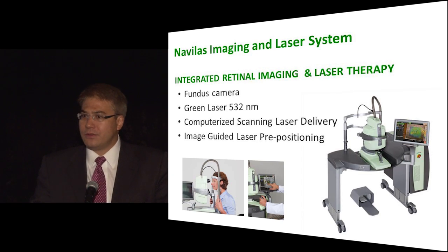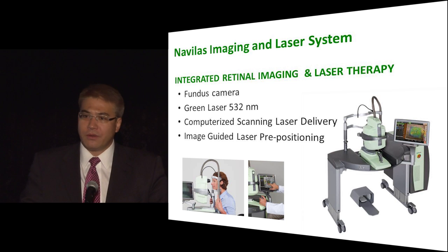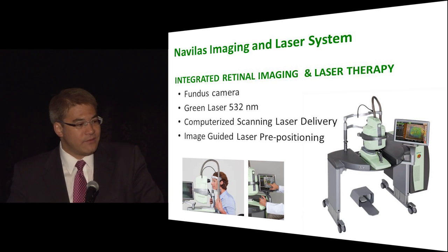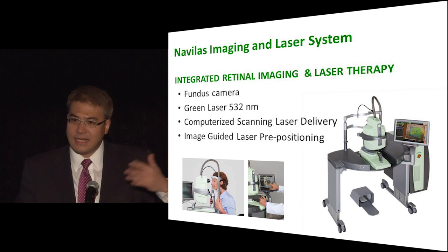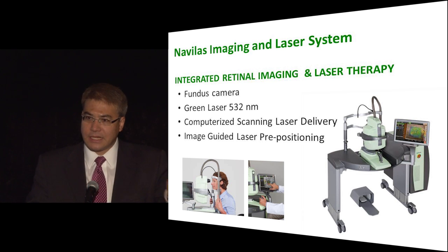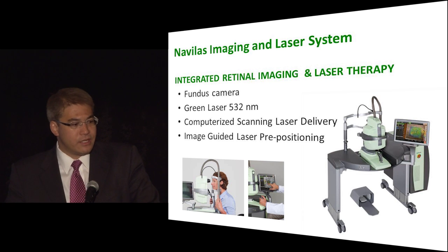So what is the Navilas? For those being introduced to this device for the first time, it's a whole new system — I call it a system because it handles the retinal imaging portion, the planning portion, and finally treatment and documentation. It has a fundus camera and a laser with computerized scanning capabilities. The eye is being tracked throughout, so you very precisely place these laser spots.